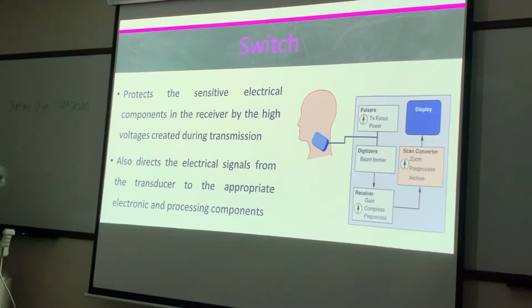Here we have our pulser, very high voltages right here. Here's our digitizer or our beamformer, right? And while we're getting these high voltages from the pulser, it's going to go to the transducer, right? That transducer is going to scan the patient, and it's going to come back to the beamformer before it goes to the receiver. This switch protects this receiver from those high voltages.